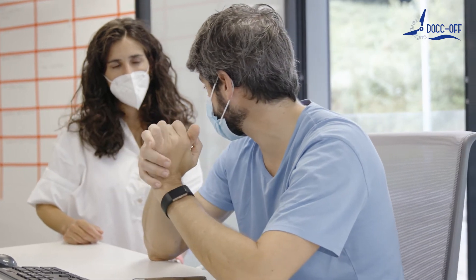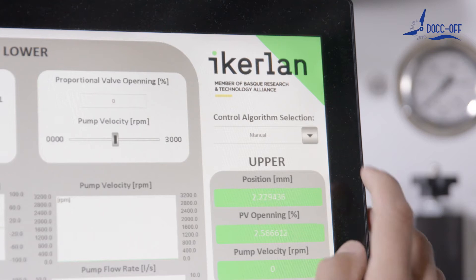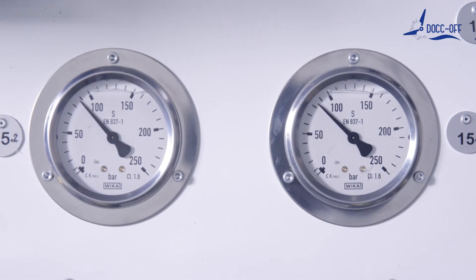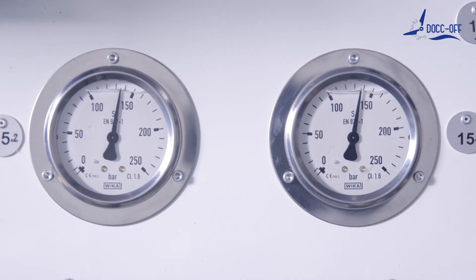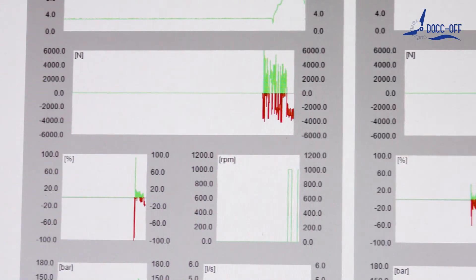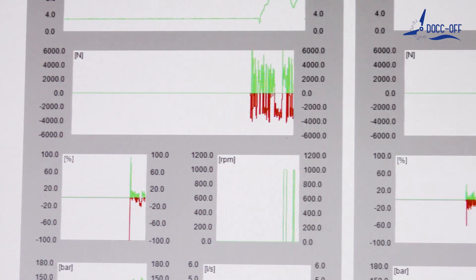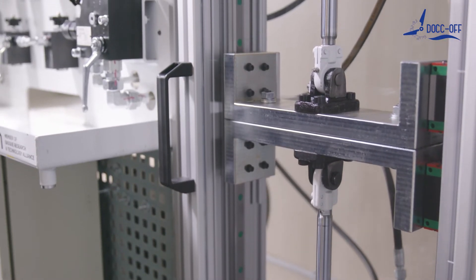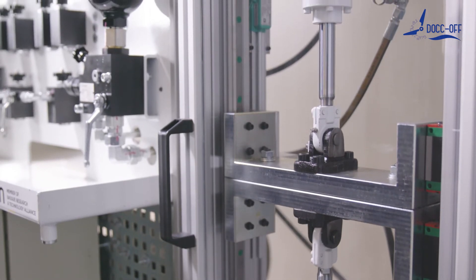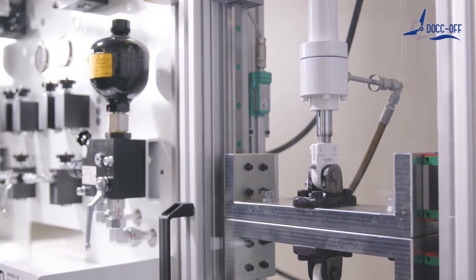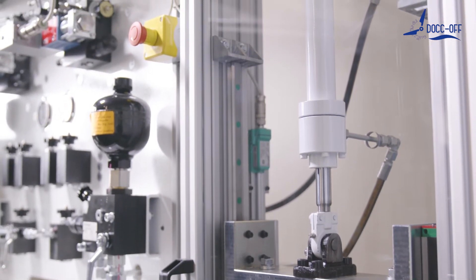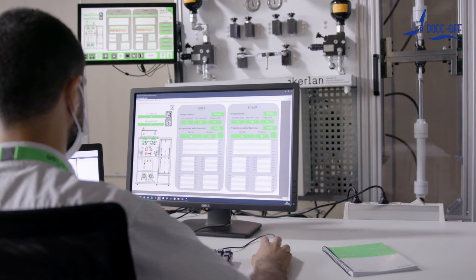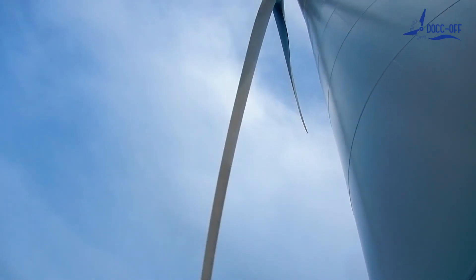The partners have tested their algorithms on synthetic data from a high-fidelity simulation model with good results, and then on sensor data from a scale prototype in the lab. The scale prototype is mounted on a test bench where it moves as on a wind turbine, while opposed by another cylinder which applies the force it would face in real operation. The prototype is equipped with needle valves to cause leaks between the cylinder chambers as well as at the pump. By running hundreds of tests with different turbulent wind inputs, DOCC-OFF partners obtain sensor signals with the same overall statistical properties as a real wind turbine. They have observed that the effects of leaks on sensor data are as predicted by their model, and that their algorithms work as well on sensor data as on synthetic data.